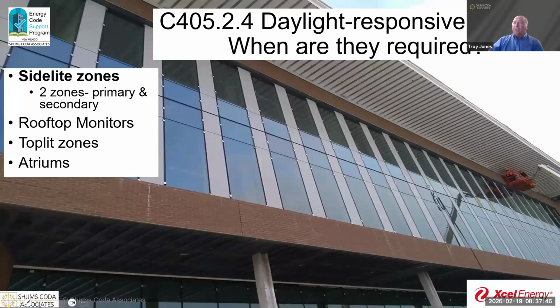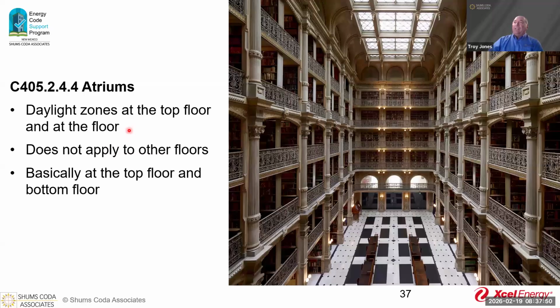So let's jump to atriums next. Daylight zones are at the top floor and at the floor. We do not apply the daylight zones to the rest of these. So if we have windows that come across and around each one of these floors, they would be addressed separately that way. But the atrium responsive requirements are only for the top floor and the bottom floor.